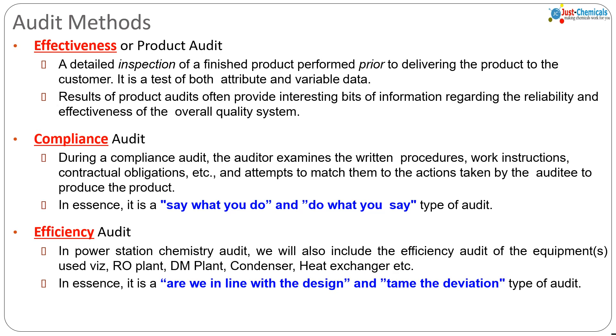In the second type — compliance audit — there may be two or even three aspects dealt with by the chemistry department. These include DM water quality against the standard adopted by the plant, steam water quality against the standard adopted by the plant, and condensate polishing unit outlet water quality against set standards. The standards may be from VGB, EPRI, or OEM standards.